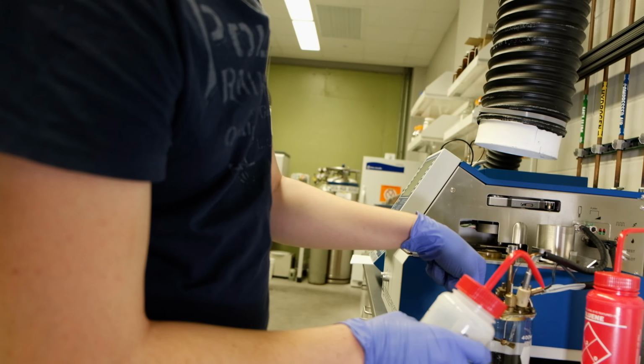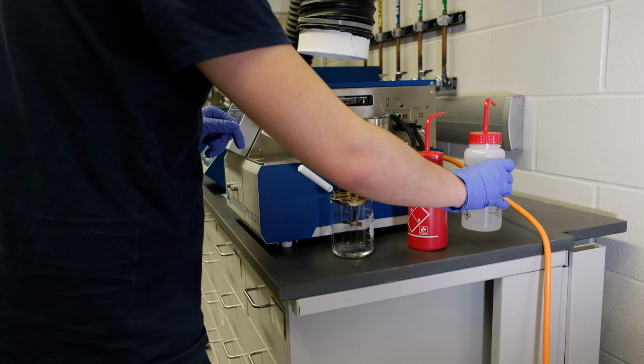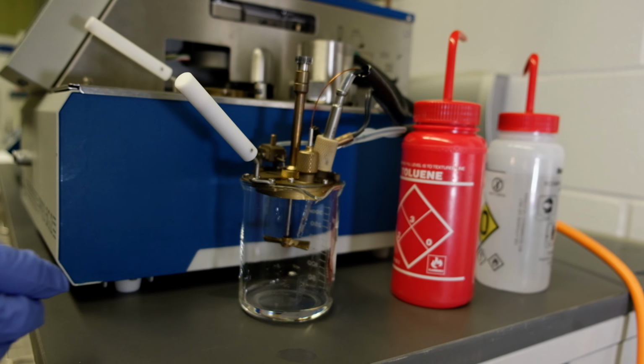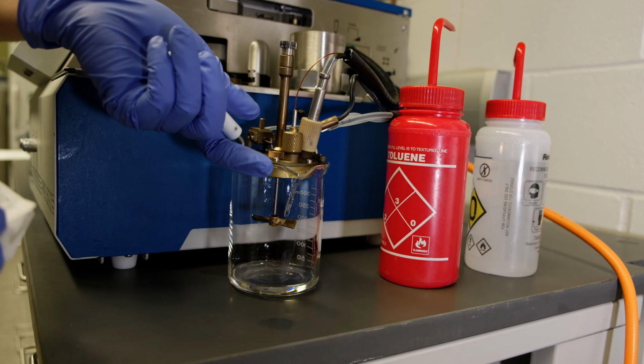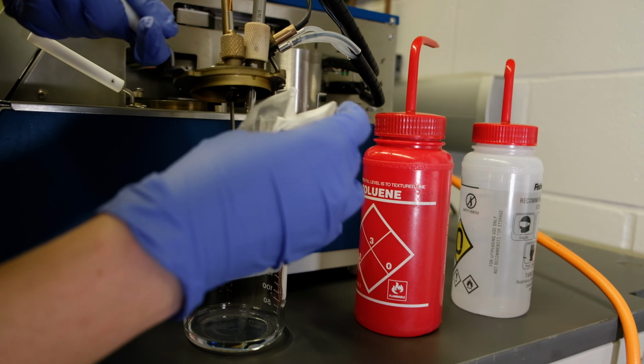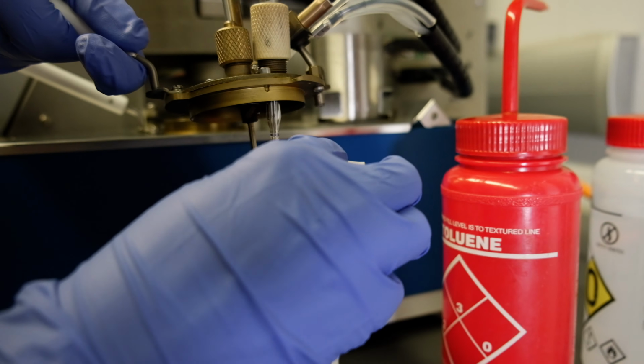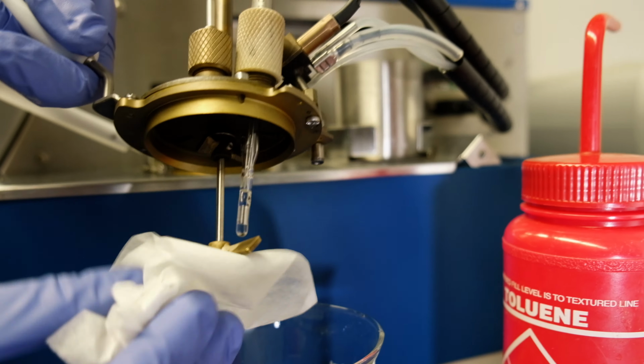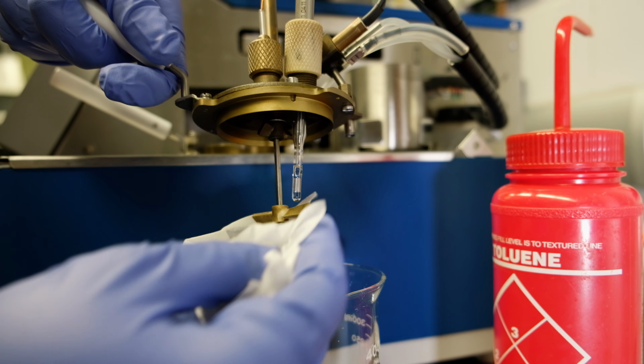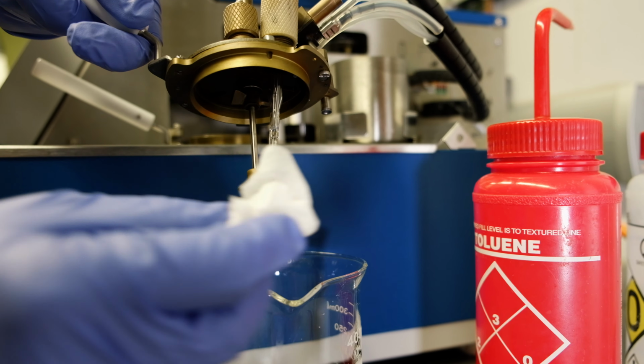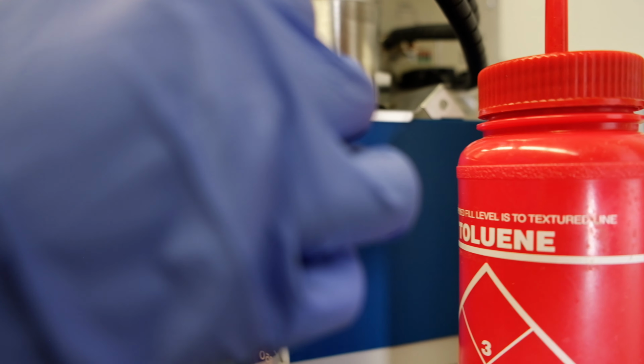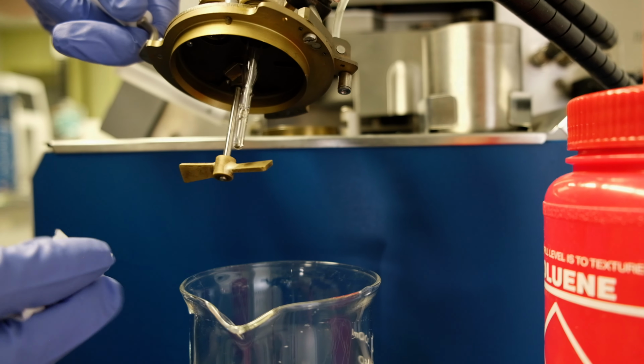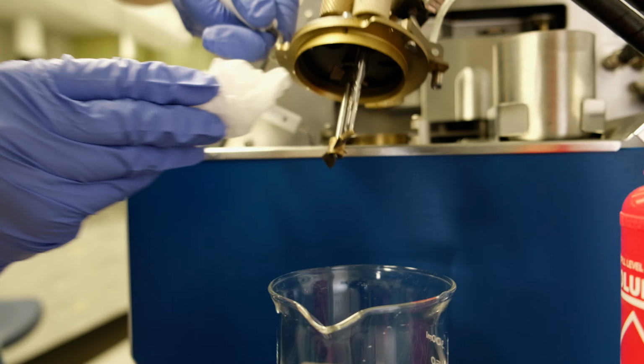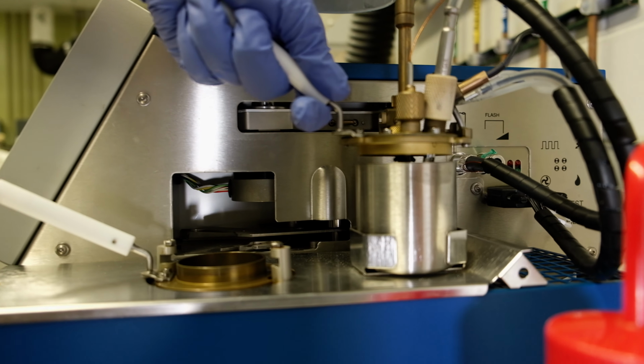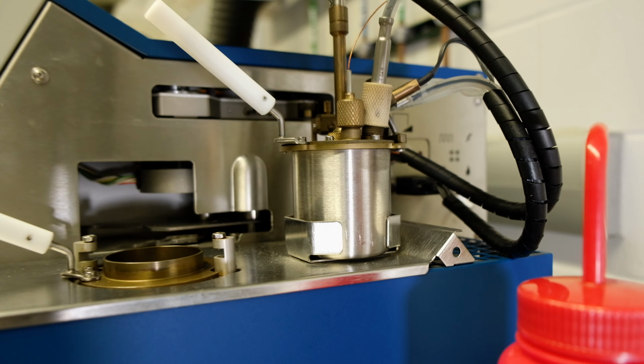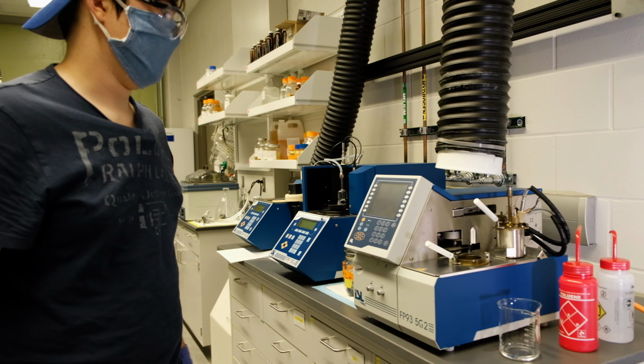And then you just leave it to dry for a little bit. To expedite the process of drying, again, you can go at it with the Kim wipes. But again, you're looking for that matte finish on the metal when you're done. And so you can see the propellers don't have any shiny, greasy looking spots on them. And it's a little bit harder to tell on the temperature probe because it's glass, but the metal is a good indication. And when you're done, this will go back into this top cup up here. And you set that down, reach around the back on the left side, shut down the machine, and you have completed the flashpoint test.